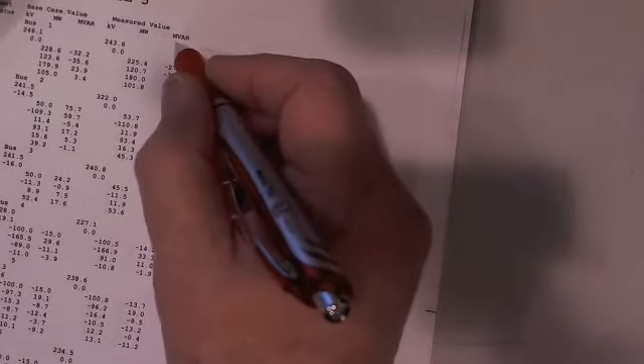And I ran the state estimator. Boom. The first time it ran, it converges to 3,595, and it says the M42, that's a flow, has a huge sigma, so take that out, rerun it, and now I'm down to 693, but that's still pretty bad. Take out this voltage on bus 2, and now I'm shooting for 61, and I've got 693. Then I'm going to take out the load on bus 6. That measurement is bad, and once I take that out, I make it so that the estimator solves.